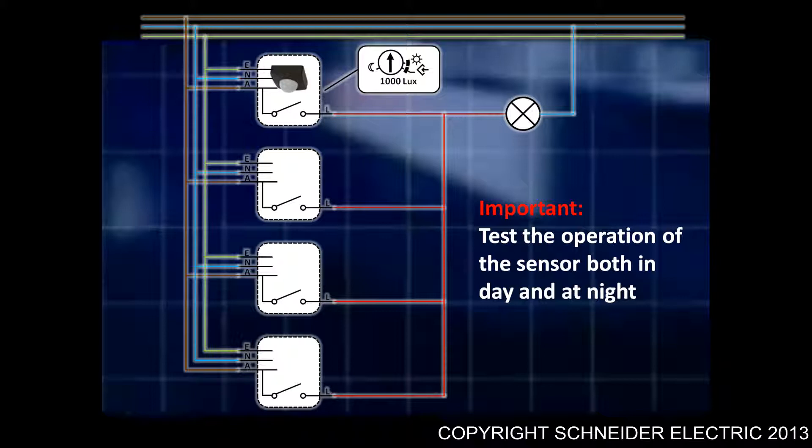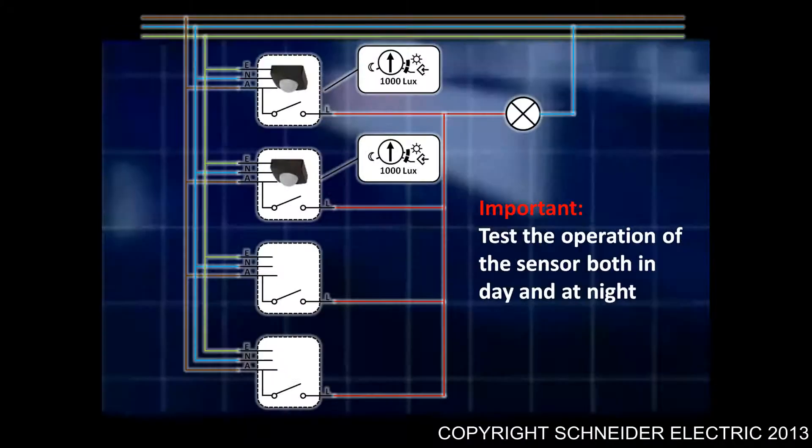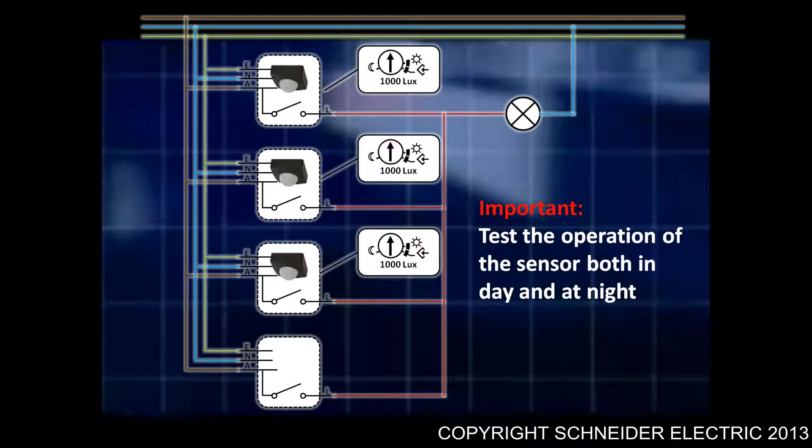What you need to do after that, and this is only once you've confirmed the operation of the first sensor, is connect up a second sensor and go through the same process. What you should find is, as you keep adding sensors, you know that every sensor you've added before should be working 100% correctly.